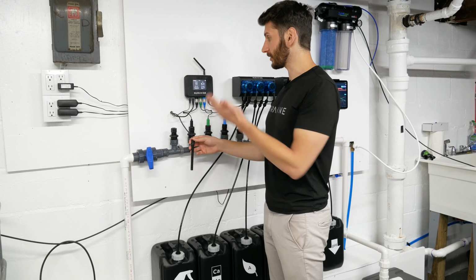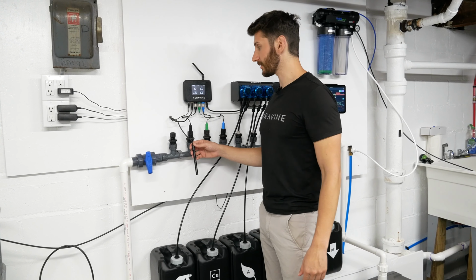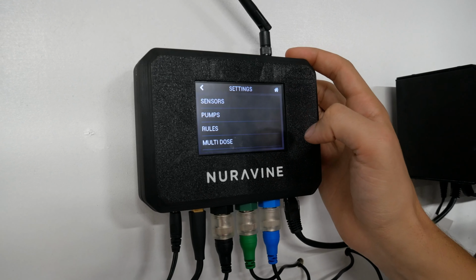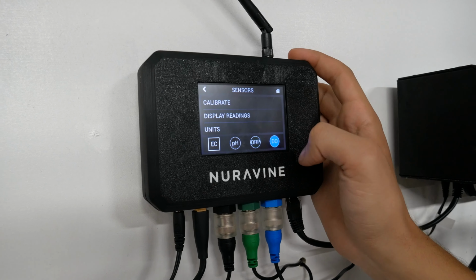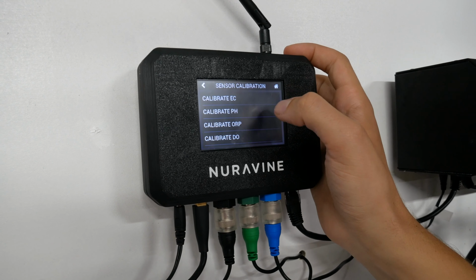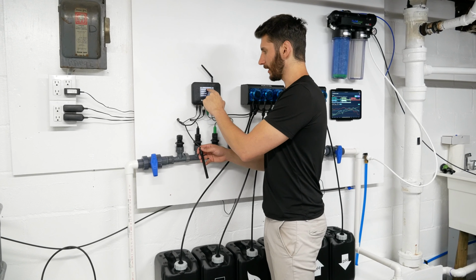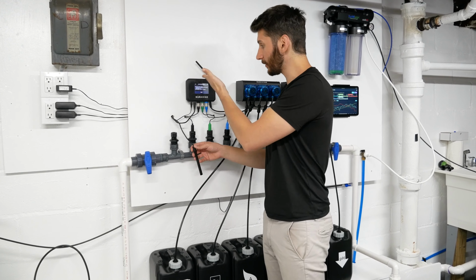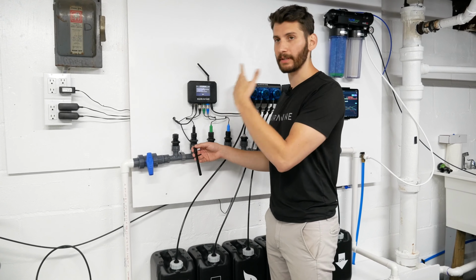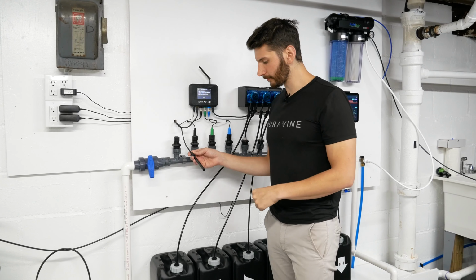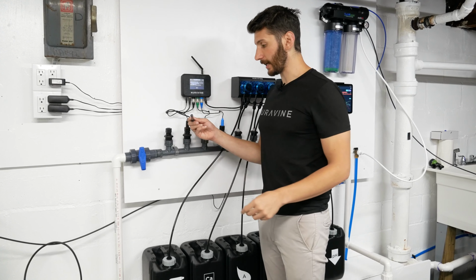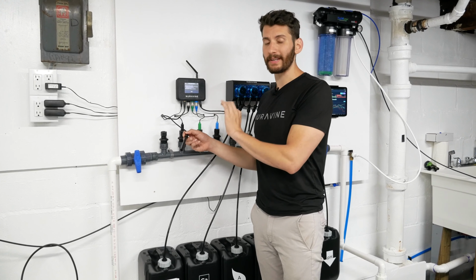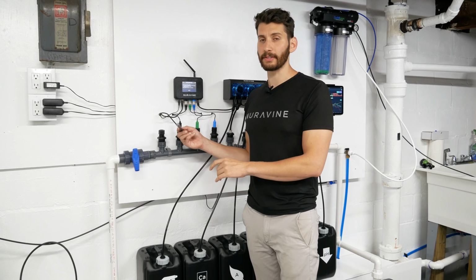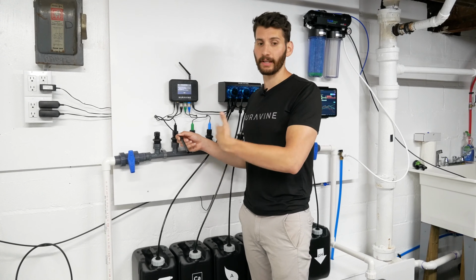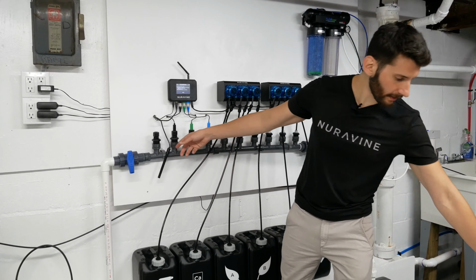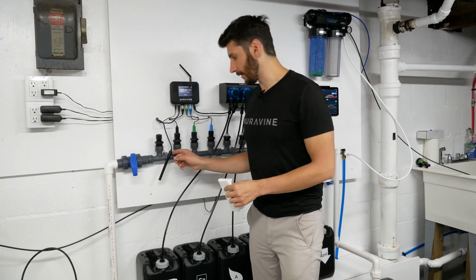The next step is we're going to go into the menu and go to the calibration section. So we're going to hit the menu button right there. Then we're going to click on Sensors and then Calibrate, and then Calibrate EC. It actually provides you with some instructions on screen, but I'm going to explain those to you in this video. Now the first step is we're going to want to clean this probe as much as possible because we're going to be doing a dry calibration, which means we're calibrating it in the air. So I'm going to go ahead and grab my cloth and wipe this down.